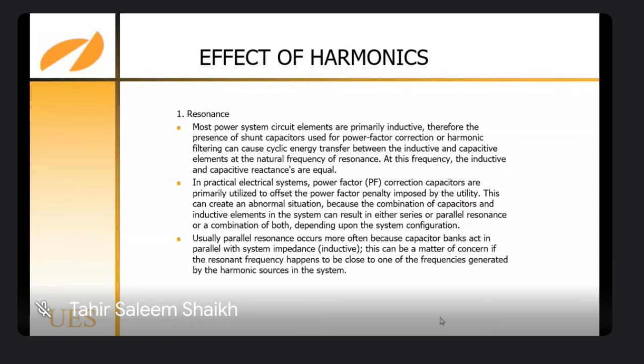This can create an abnormal situation because the combination of capacitors and inductive elements in the system can result in either series or parallel resonance or a combination of both, depending upon the system configuration. Usually, parallel resonance occurs more often because capacitor banks act in parallel with system impedance. This can be a matter of concern if the resonance frequency happens to be close to one of the frequencies generated by the harmonic sources in the system.